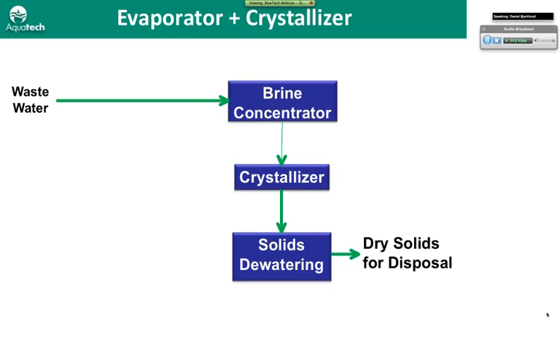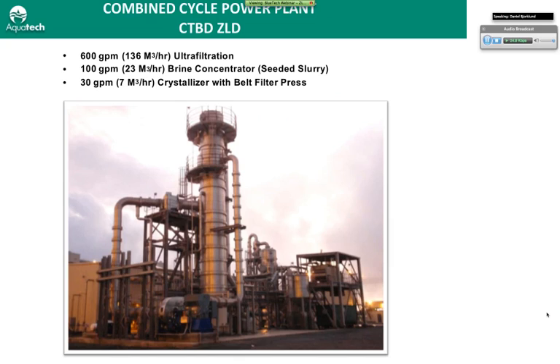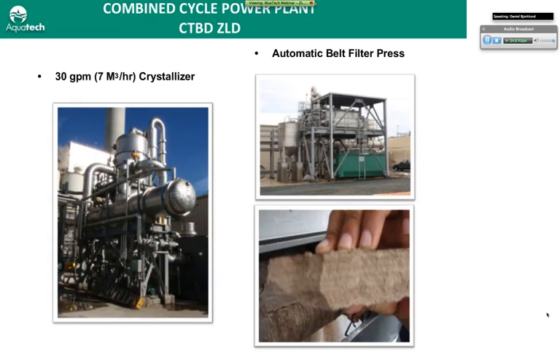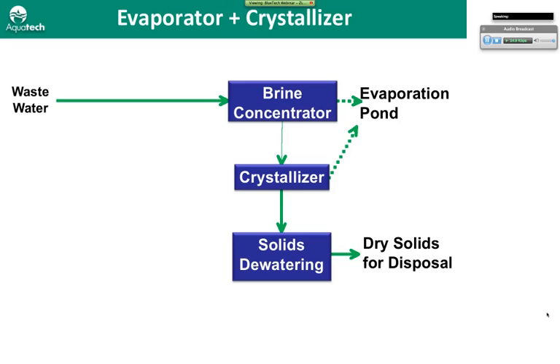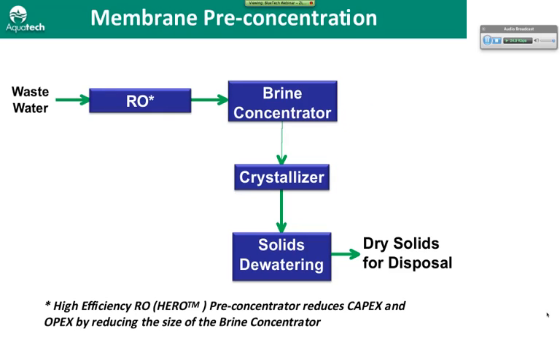Some of the typical configurations, very traditionally, you'd have a brine concentrator, which would blow down to a crystallizer, and then some sort of solid dewatering device, whether it be a centrifuge or a belt filter press, and eventually dry solids. And these are some photographs of some typical systems. And there are some options to that. If you have the ability to have an evaporation pond, you can cut down on your CapEx and OpEx by blowing down directly from the brine concentrator to the evaporation pond and eliminate the crystallizer and the solids dewatering. Or you could put in a smaller evaporation pond and blow down directly to it.